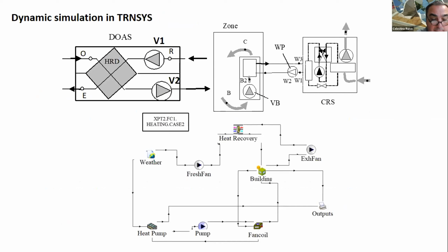An important simplification was adopted in the present study. Instead of simulating all rooms and the associated system, an equivalent system composed of only one representative room and the associated air conditioning system was considered. Obviously, in a real context, if the thermal loads of different rooms are different, this approach would not be valid. All the system should be simulated.